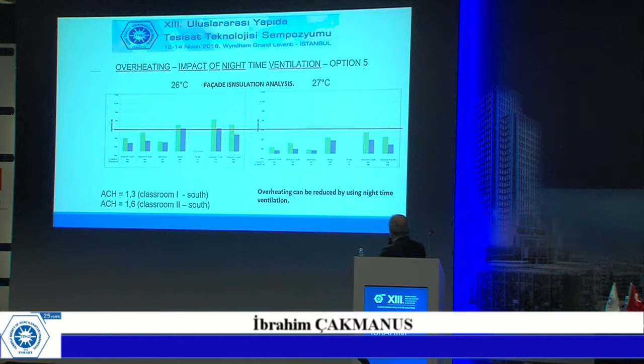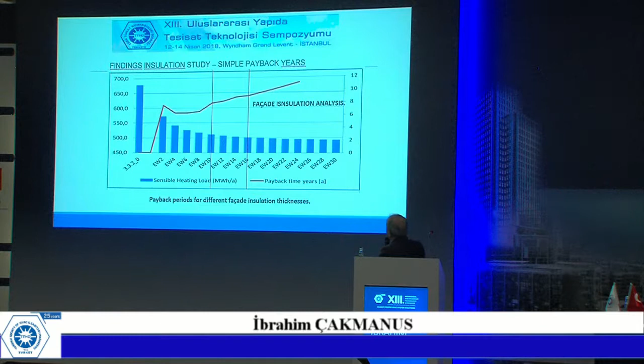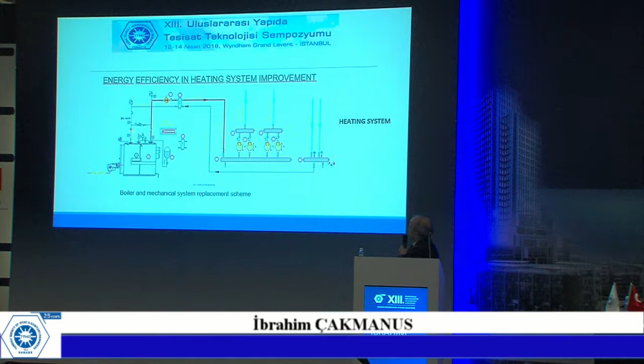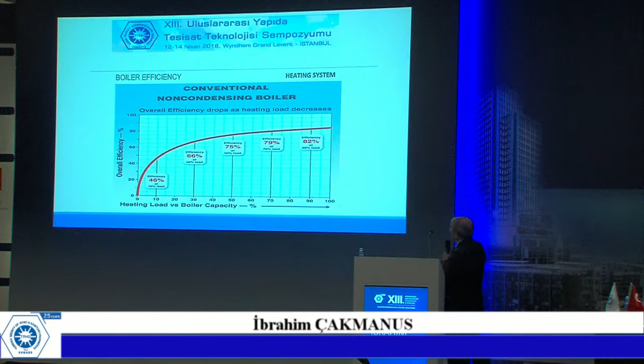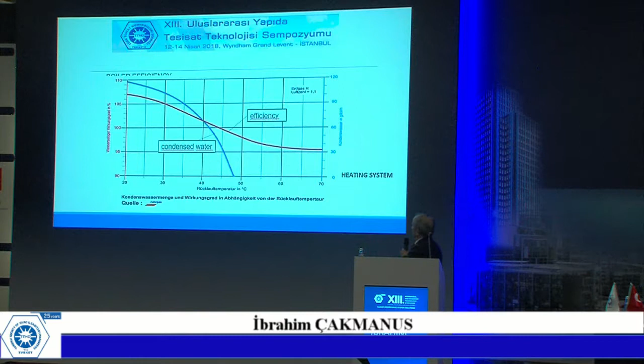If we insulate the facade of the building, in summer there may be overheating problems, of course, because at night the building cannot be cooled down. Here also there is an overheating problem, and here are payback periods for insulation. The existing heating system should be replaced with condensing boilers and thermostatic valves for schools, residential schools. A non-condensing boiler has a maximum efficiency of approximately 80%. If we use a condensing boiler, we can reach very high efficiency, because we insulate buildings and can use this type of boiler.